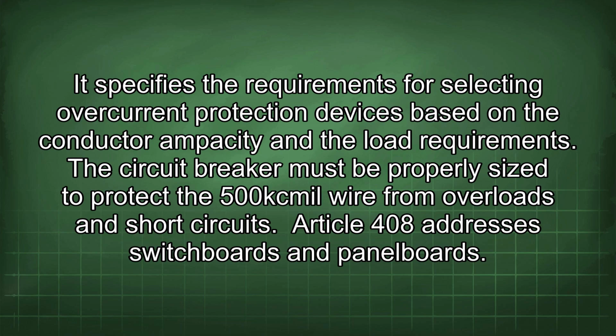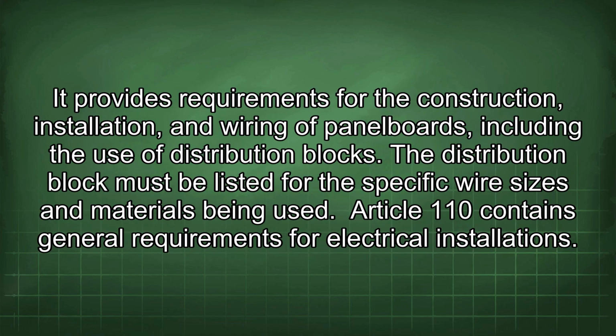Article 408 addresses switchboards and panel boards. It provides requirements for the construction, installation, and wiring of panel boards, including the use of distribution blocks. The distribution block must be listed for the specific wire sizes and materials being used.